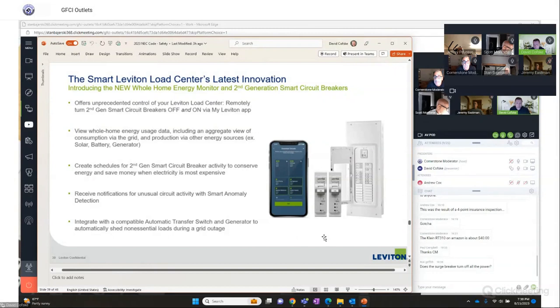So on our second generation breakers, from the app, I can go into a breaker and turn that breaker on and off from my phone. I can also set up a schedule inside the panel. So if I had an irrigation system, or a pool shed that I was protecting on a GFCI circuit, I could say, hey, I want to shut power off in that panel from dusk to dawn. I don't want any power going into that shed. I can set a schedule inside the circuit breaker, really eliminating a time clock. Back in the day, that's how you used to have to control things, through a time clock. But now technology allows us to do it right within the circuit breaker.